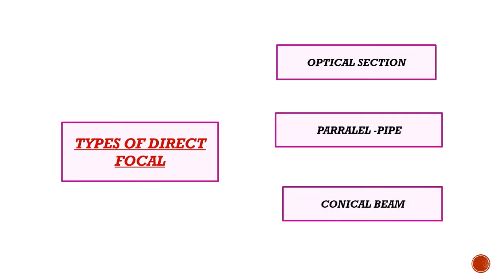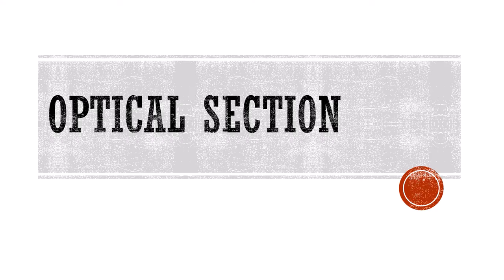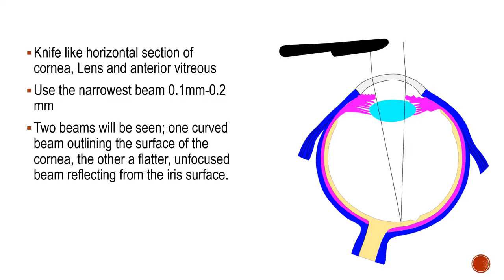Direct focal illumination can be of three types: the optical section, the parallel pipe illumination, and the conical beam. The optical section creates a knife-like horizontal section through the cornea, lens, and anterior vitreous. You can take sections at the corneal level, lens level, or anterior vitreous level. For the optical section, the beam must be very narrow — approximately 0.1 to 0.2 millimeters in thickness — which is very important.